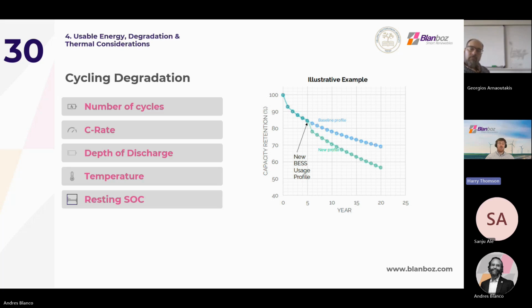This can be thought of in 2 ways. If you have a 4-hour system rated at 25 megawatts, which equals 100 megawatt hours of discharge capacity, versus a 1-hour 100 megawatt system, which also discharges 100 megawatt hours but in a much shorter time frame, the 1-hour system will face the larger degradation.